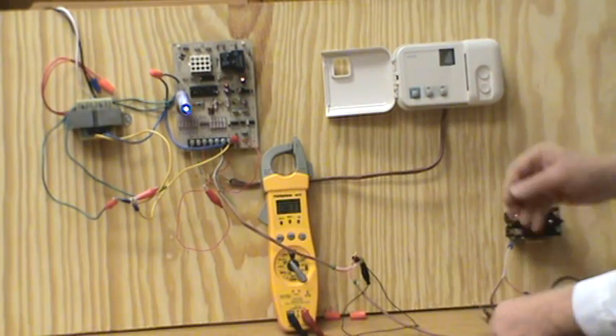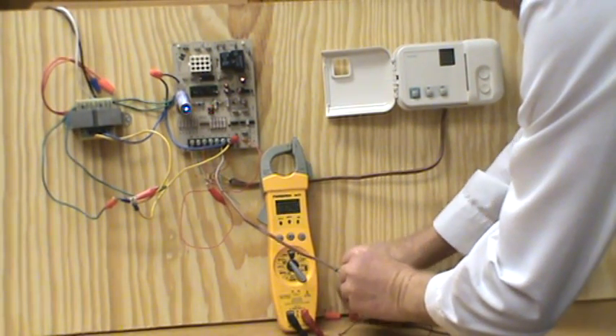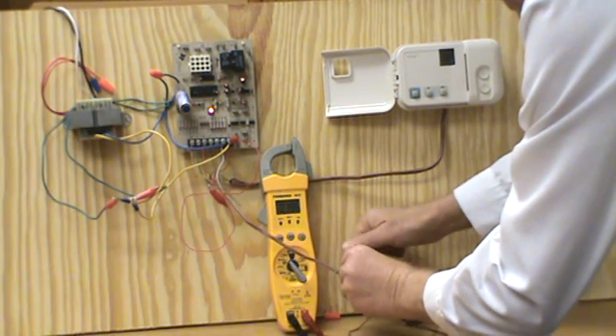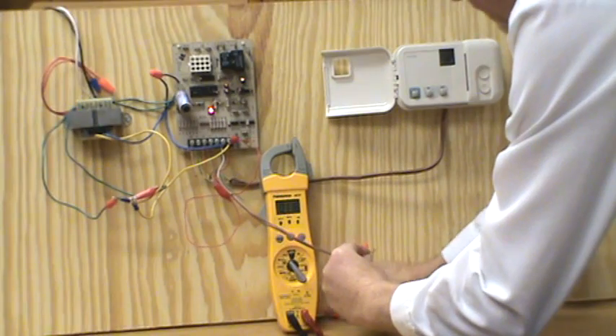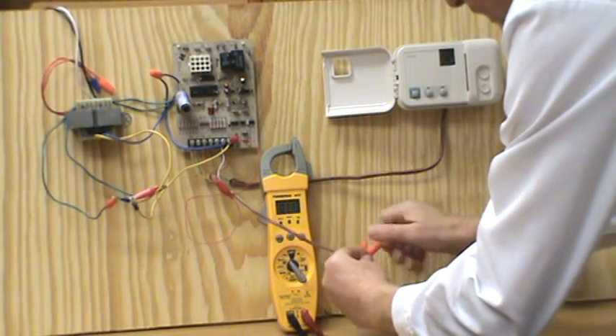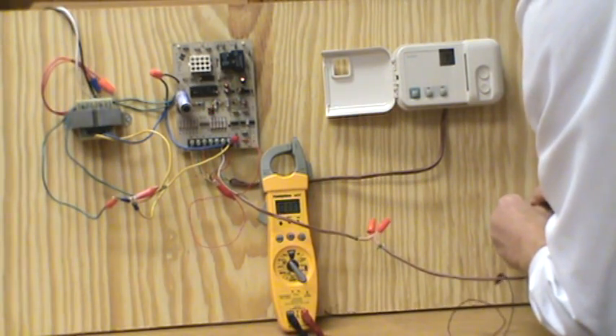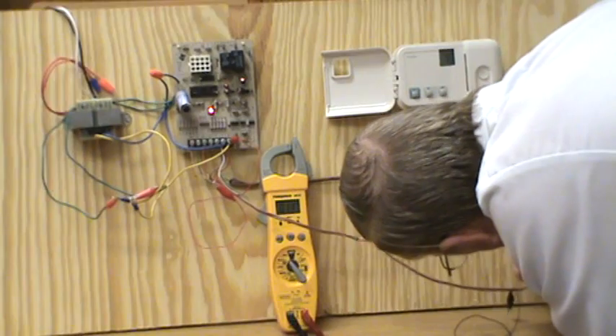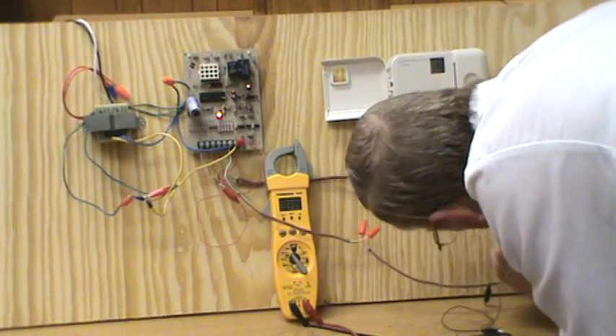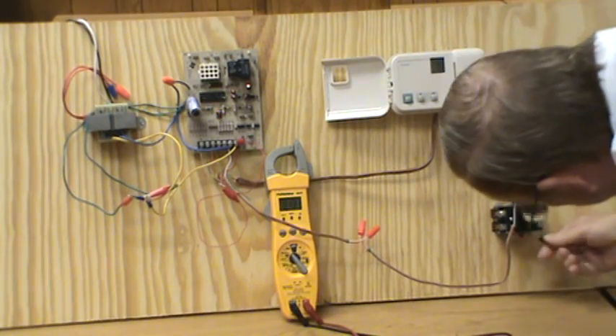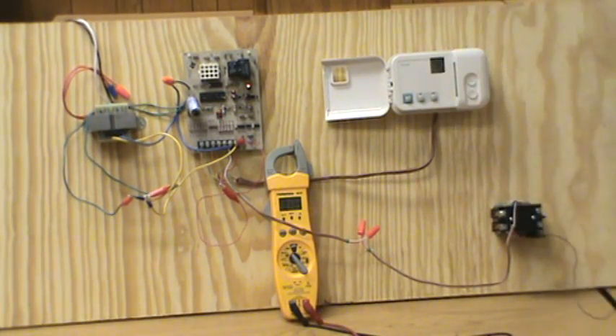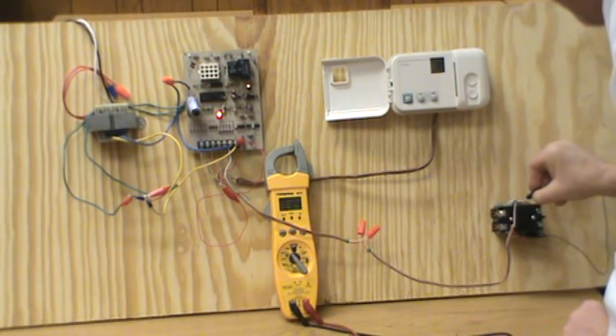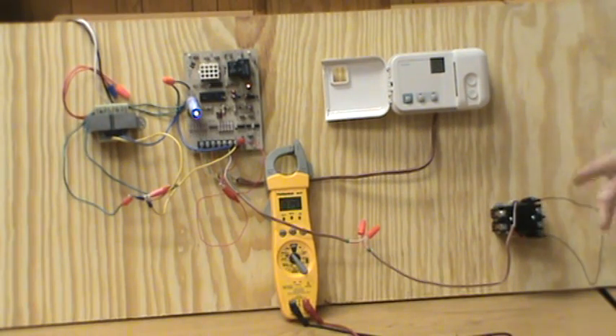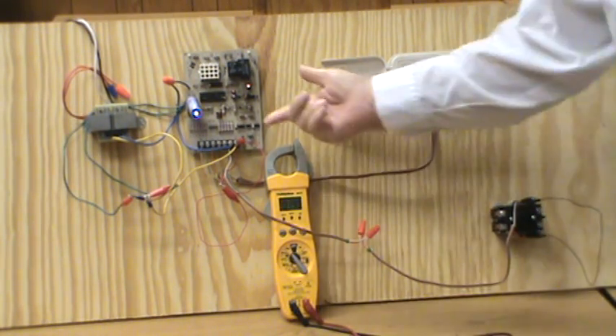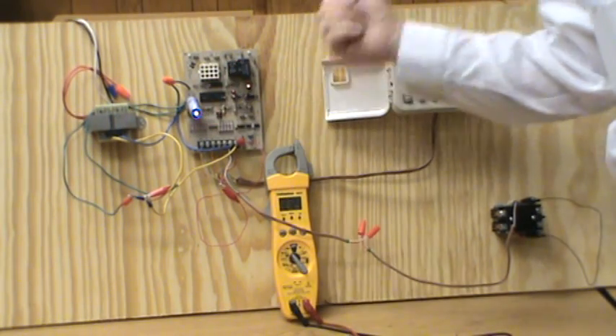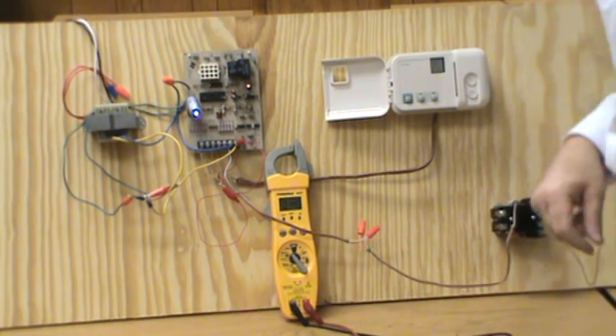Now if I were to take the short across the wiring in the attic, and let's just say that we've got a short inside the condenser, and I can put one across the coil of the contactor. We've already found one type of short in the wiring going out to the condenser. Let's just find something that's inside the condenser. I put the short across the coil of the contactor itself, and you can see the LED light is lit up because we've got a short on that cooling circuit on the contactor inside the condensing unit.